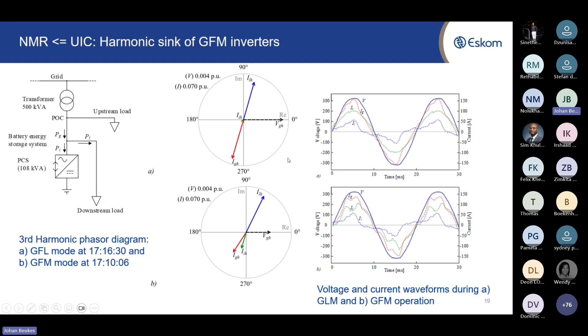In this study, we showed the superior performance of grid forming with a real installation in terms of harmonics. And then just to conclude, we are developing grid-forming BESS specifications at the moment, and we basically use FinGrid. We don't have a formal specification yet, but we basically use these two documents, which are very good documents in developing these requirements or specifications. That is the FinGrid one and the Australian specification for grid-forming inverters. These are the two documents if you want to know more about it. It's basically dealing with response, damping out oscillations, and things like that. That basically concludes what I wanted to say.